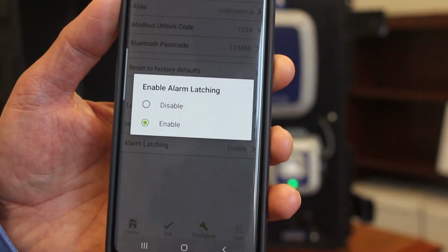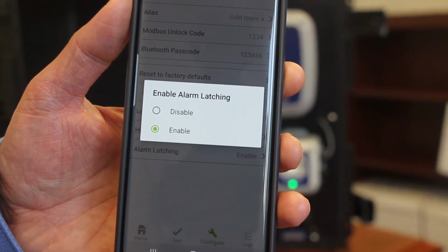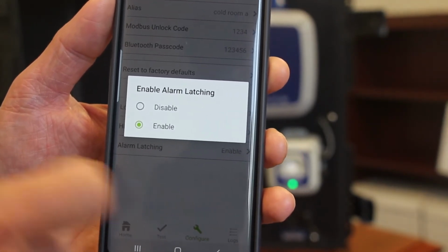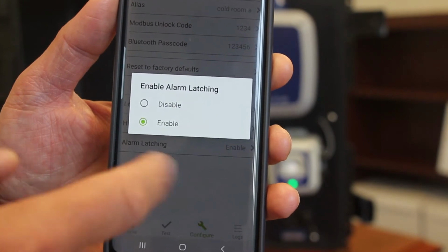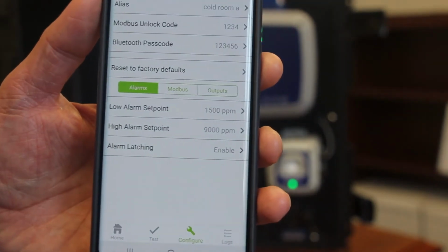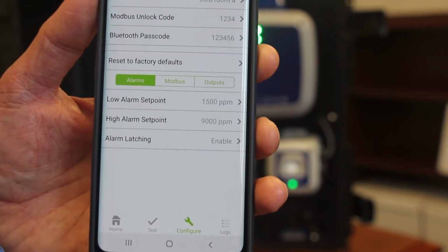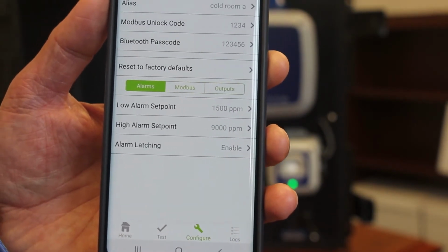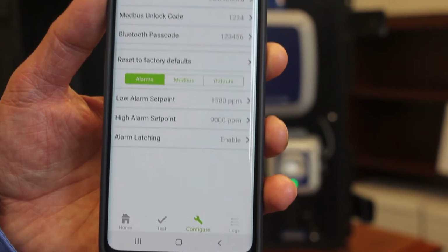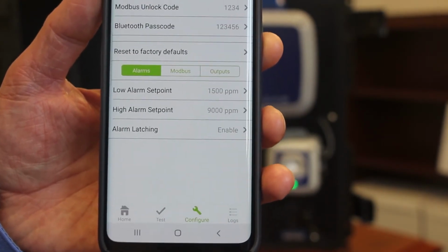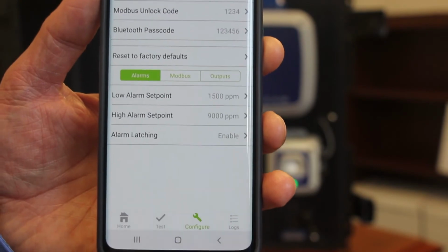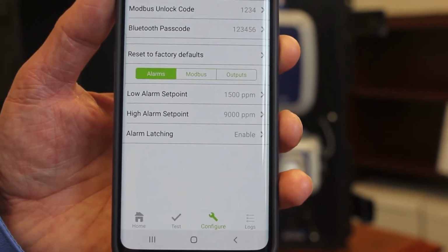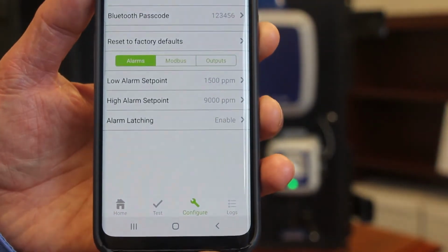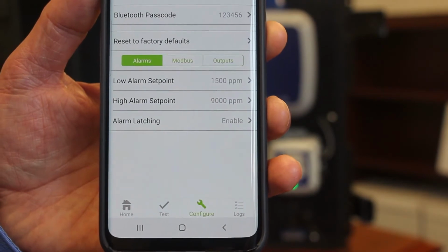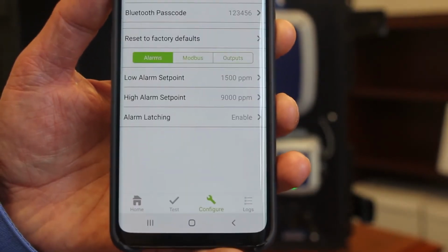The alarm latching set point you can set in here to enable or disable latching. So just as a note on this, if an alarm latches, what will happen is if you have a refrigerant leak, the sensor sees that refrigerant leak, the concentration exceeds the alarm level, the detector will go into alarm. And it will stay in an alarm until someone physically acknowledges that alarm on the system itself. So that's a latched system, and that's specifically called out under ASHRAE 15. And that's also quite typical for a number of customers in terms of how they have the unit configured.